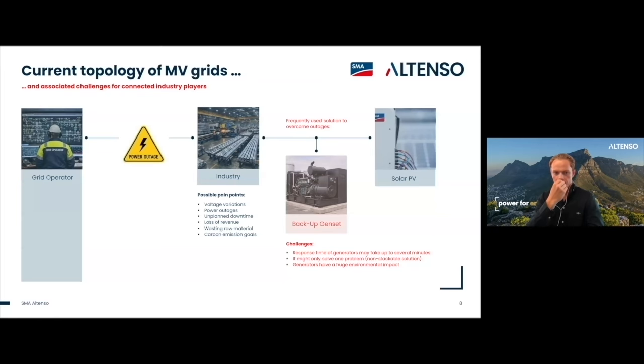So just to provide a little bit of an overview of what the current topology of medium voltage grids would be, essentially your mining companies or industrial companies would typically connect between 6.6 and 33 kV and rely on Eskom or municipal supply, but then have a diesel genset as backup. So a Wood Mackenzie report I saw indicated that there's conservatively over 100 gigawatt of installed diesel genset capacity in Africa. And other sources indicate that over 10 gigawatt of that can be attributed to the mining sector. So that's the sort of normal layout in the African industrial context.